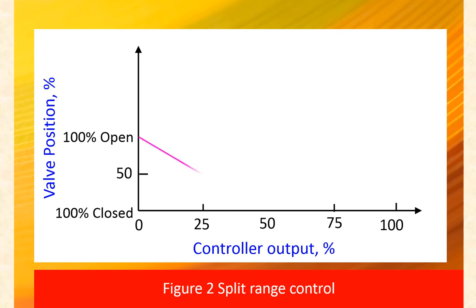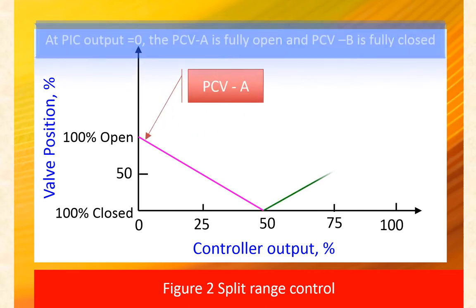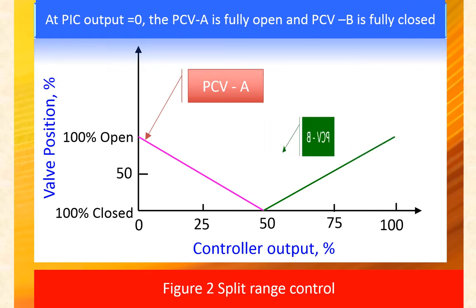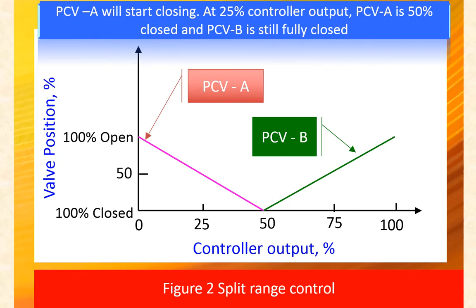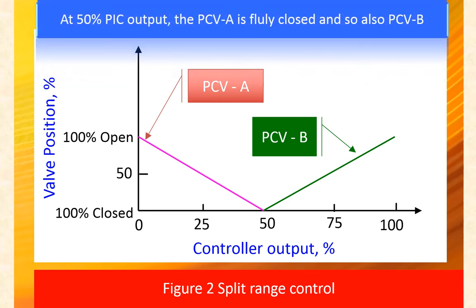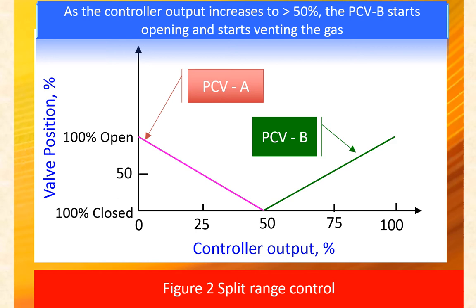This figure illustrates the function of a split range control valve with a valve opening versus pressure controller output diagram. Initially, control valve PCVA is fully open and PCVB is fully closed. As pressure increases above the set point, the controller output starts increasing from zero and PCVA begins to close. At 25% controller output, PCVA is 50% closed and PCVB is still fully closed. As controller output increases above 50%, PCVA goes to full close while PCVB starts opening.